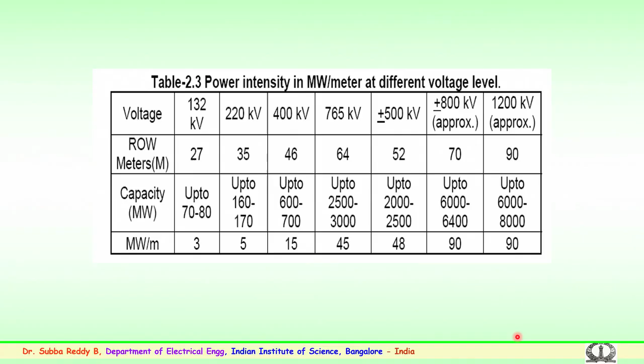But for a similar voltage level, when you look at plus minus 800 kV DC, the right of way and the power transfer capability for DC are much higher compared to the AC level. That is one of the advantages of going in for long distance transmission, apart from several others. You can transfer bulk power anywhere between 6000 to 6500 megawatts in the case of an 800 kV system, and that is the advantage. So, this gives an idea of the minimum right of way for towers at various voltage levels, and the capacity of power transfer at those voltage levels.